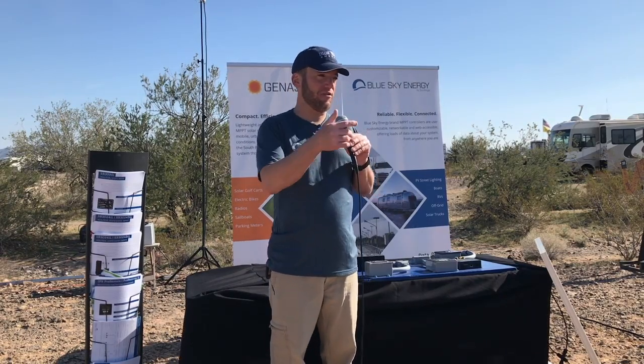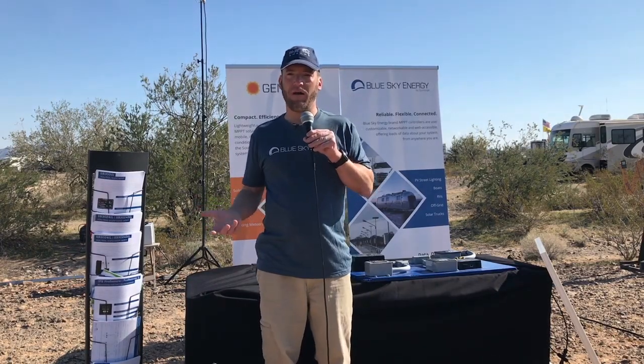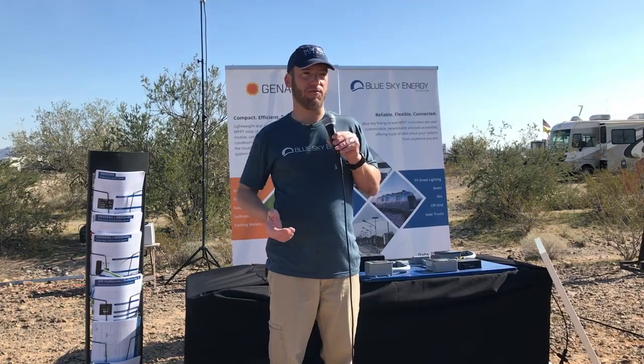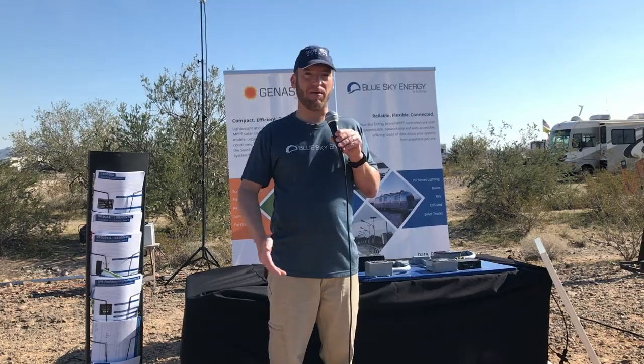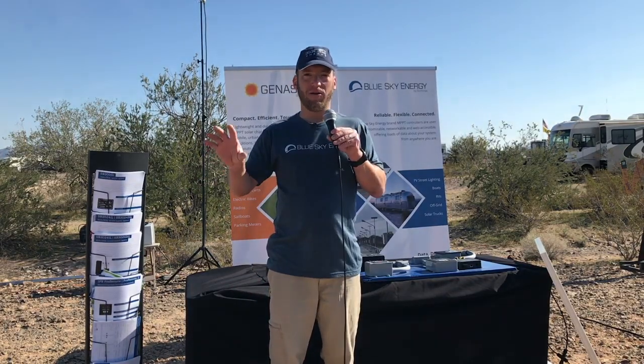So you could have an LVD between the controller and the battery, and they're not expensive, especially one rated just for that connection, not for a massive amount of current. Blue Sea makes a real nice one, about $80, rated 150 amps, or really 80 amps continuous, 150 for 5 minutes intermittent. That's just one way you could solve that problem.